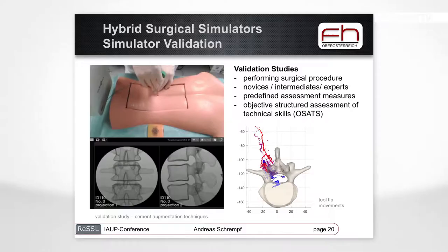We also work on other aspects such as cement distribution. When a cannula introduces cement into the vertebral body, the cement distributes within the vertebral body in a pattern that depends on the structure of the cancellous bone. We compare the cement distribution on a human vertebra with distribution on our artificial vertebra during different stages of cement application. This is the biomechanical validation of the mannequin side.